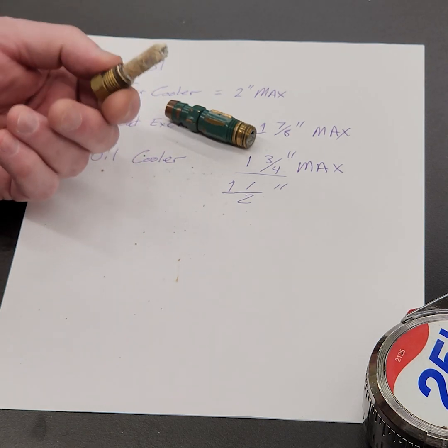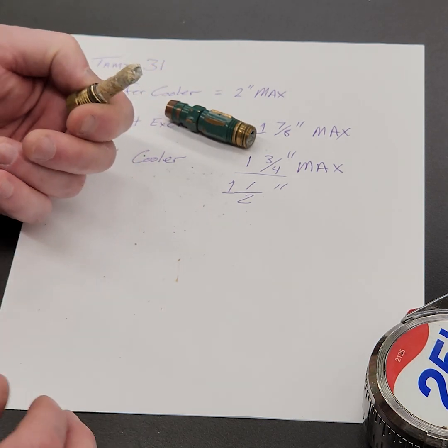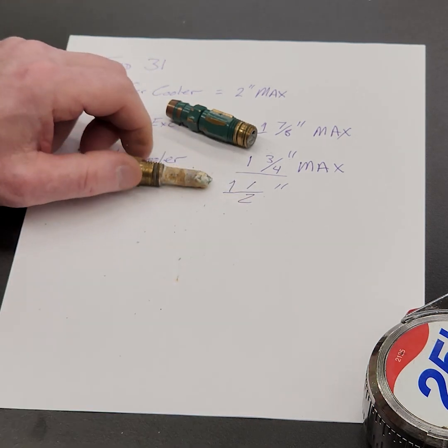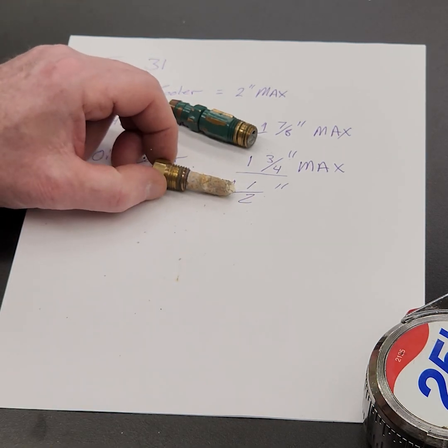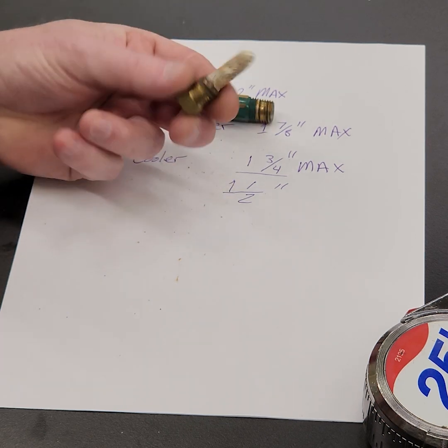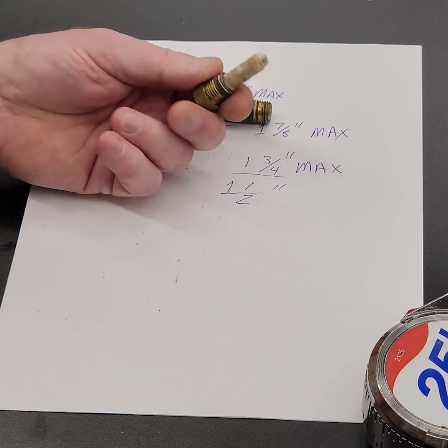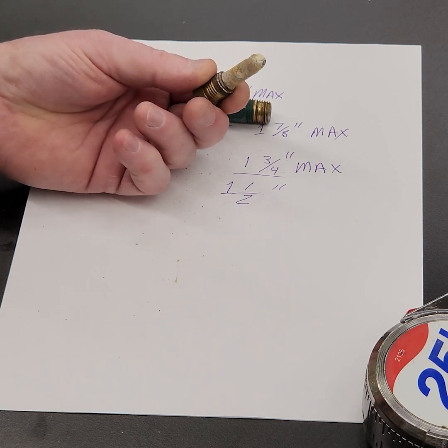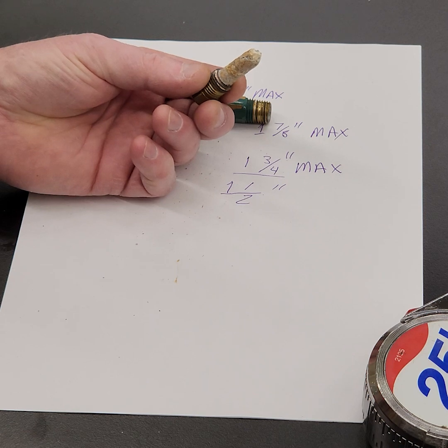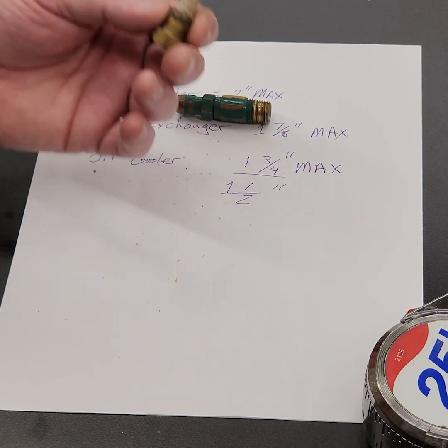A little bit of Teflon tape on the threads and just lightly seat these. So what I always say is I always turn these in until they get snug. And then I do a quarter turn, no more than a quarter turn. So do not crank these in tight with a wrench. Just bring them in until they're snug, until they just start to get snug. And then no more than a quarter of a turn. Because you don't want to split the housing. That's another thing that novices will do.